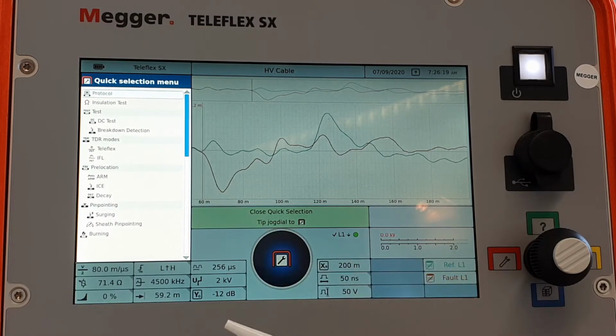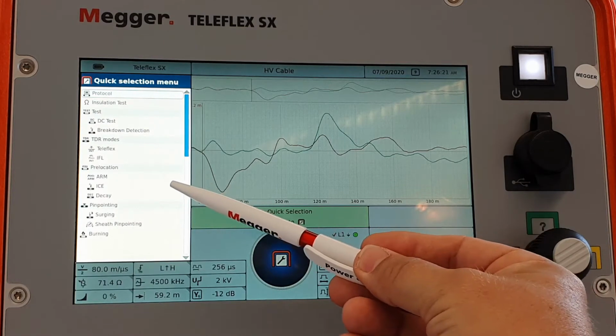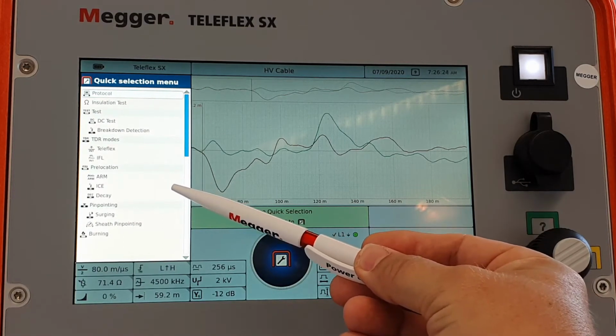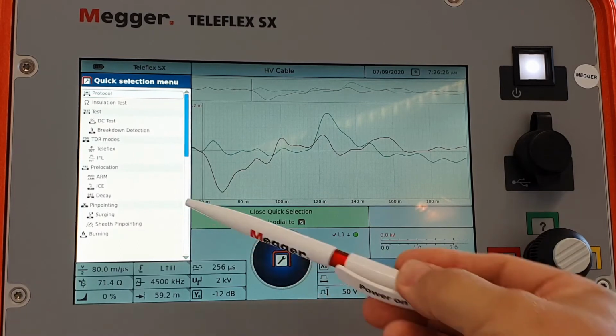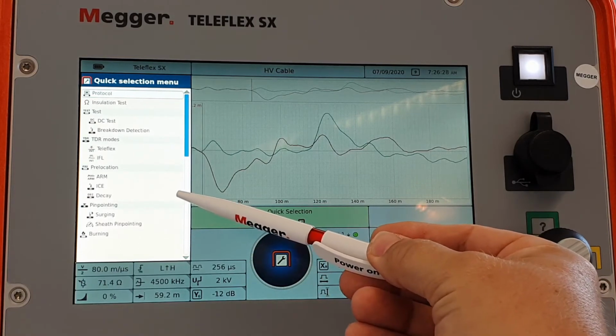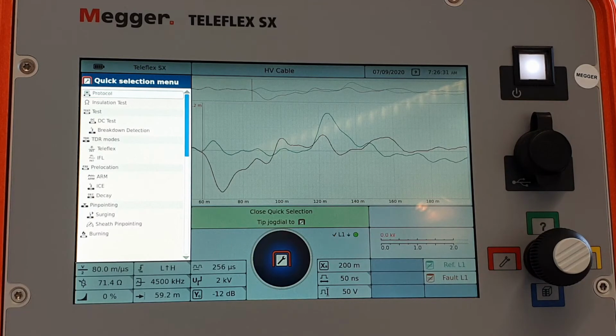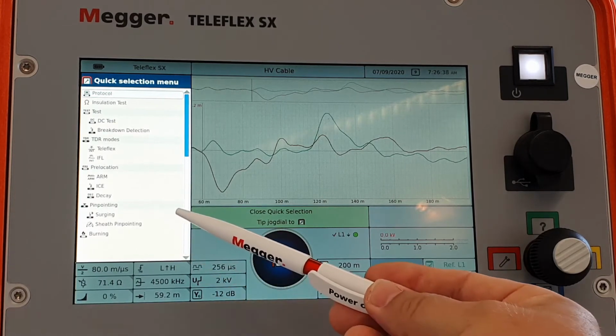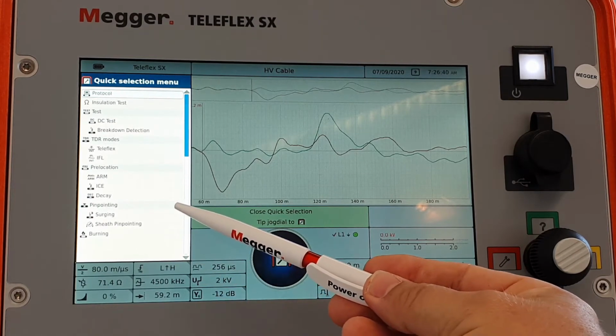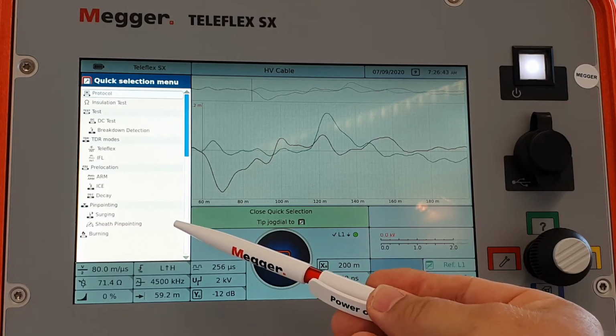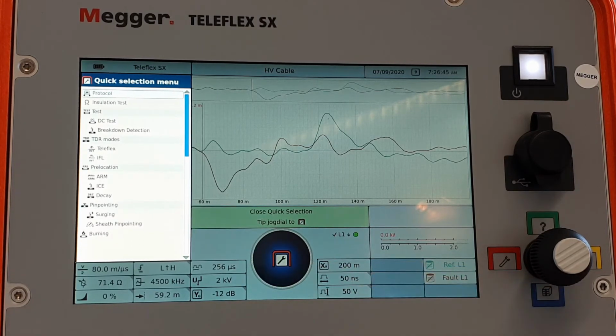If you run into problems with that, you still have the option of the impulse current equipment method, which is a bit more powerful, or the voltage decay method, which allows you to go up to 40 kV because it's using the DC test setup of the instrument. And for pinpointing, you have the normal acoustic method with a surge generator. You have sheath fault location or any kind of ground fault. And you have a very nice and powerful burning feature with 700 milliamps, which is really a lot for a small unit like this.